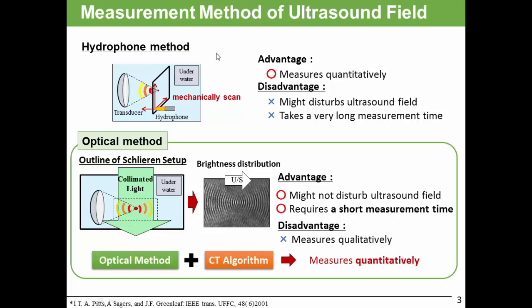In contrast, another alternative method that catches our attention is optical method. In optical method, we let the collimated light pass through the ultrasound field and acquire the image by camera. The acquired image gives you the brightness distribution. Optical method might not disturb ultrasound field and requires a short measurement time. However, the disadvantage of the optical method is to measure qualitatively. Based on the advantage and disadvantage, our motivation is to apply the optical method and combine it with CT algorithm to quantitatively measure the ultrasound field.